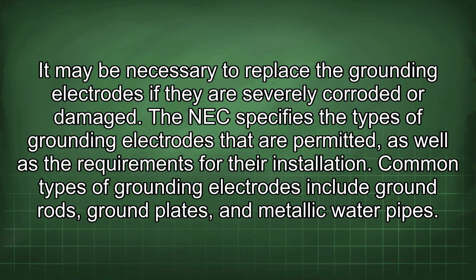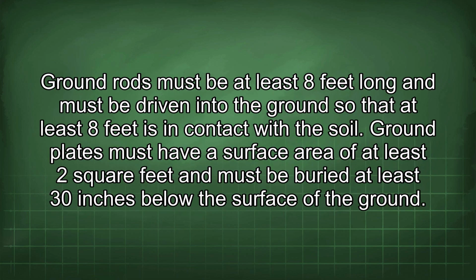Common types of grounding electrodes include ground rods, ground plates, and metallic water pipes. Ground rods must be at least 8 feet long and must be driven into the ground so that at least 8 feet is in contact with the soil. Ground plates must have a surface area of at least 2 square feet and must be buried at least 30 inches below the surface of the ground.